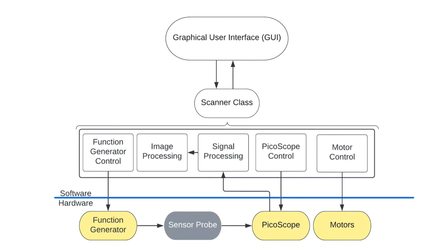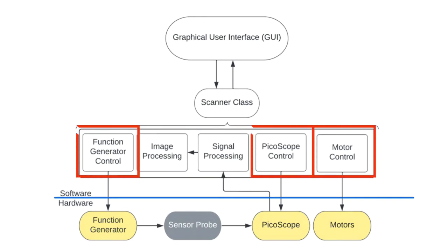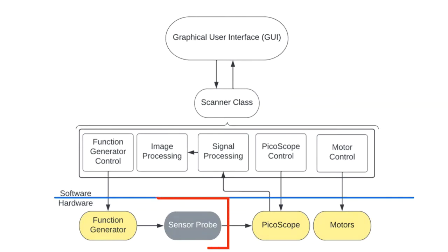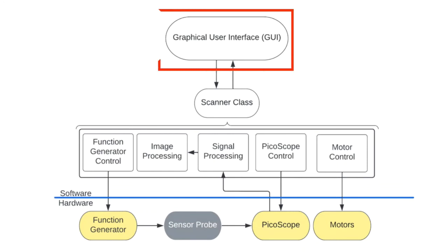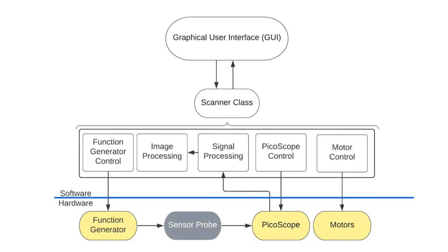Operation of the scanner is completely unified by a single software solution written in Python and C. It performs the signal and image processing algorithms discussed, as well as controlling the hardware peripherals that consist of the motors, the high-resolution ADC, and the signal generator that sends the input signals to the illuminating coil and the sensor. The scanner is operated through an intuitive graphical user interface, and the software then translates the user's desired scanning parameters into the required input parameters to each of the hardware and software components.